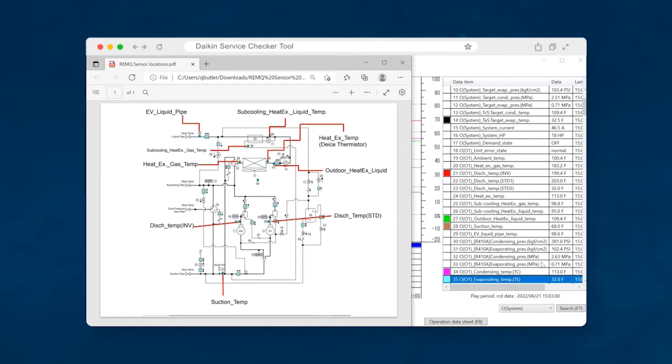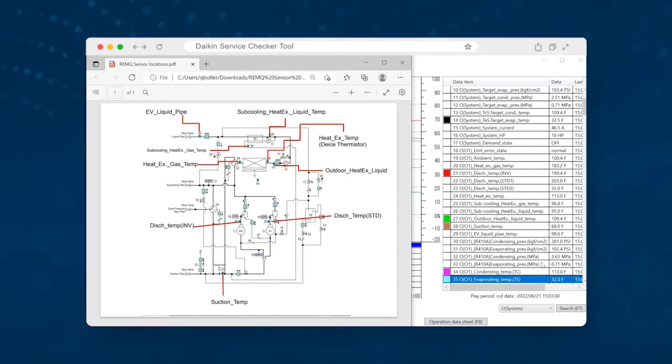So we just mentioned that the range is 27 to 82 on a VRV3. So this is a VRV3 system. And so right off the bat, we see that that value is higher than the allowable range. This can be caused from a couple of different things. One of them, the most common is shortage of refrigerant charge. The second will be shortage of oil. Now we're already looking at a system that we assume is low on charge.